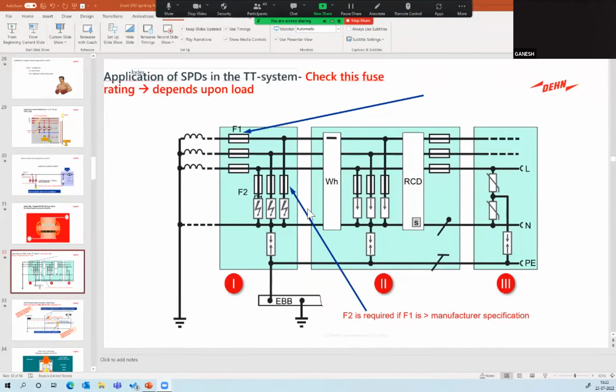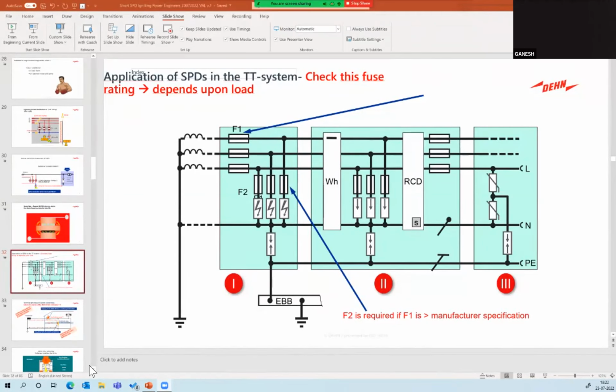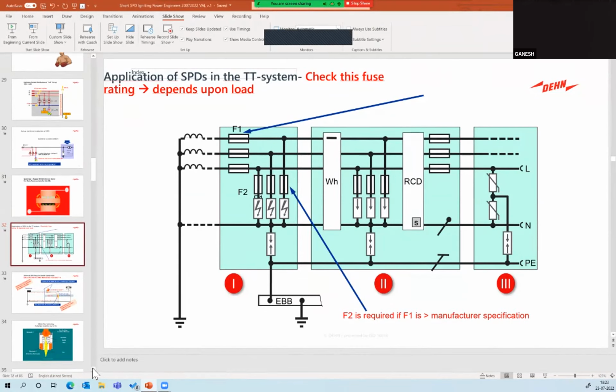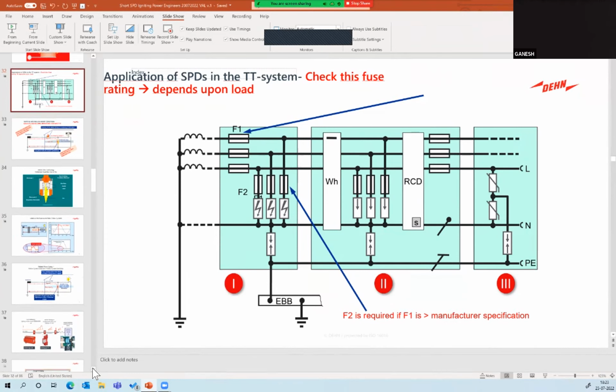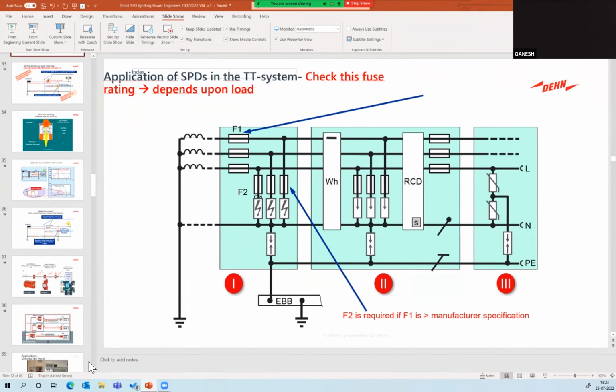Actually, I have one question regarding SPD. When the SPD is healthy, it is in green position. SPD class B, class C, right? If it is faulty, it will become red color. So after that, we have to replace the SPD, right? My question is, do we have to remove it? Is there any design for not removing it and reusing it, like an MCB? It will trip and we will reset it.